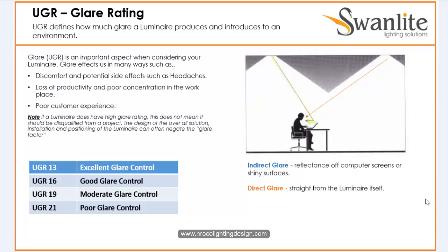In the table here, UGR 13 is an excellent glare control fitting. If your fitting has UGR 13, it means it's not glary at all — most fittings like this are very diffused and well protected in terms of optics. I haven't personally seen a fitting with UGR 13 yet, but they may exist. UGR 16 means good glare control — again, typically a direct-indirect or diffused fitting.